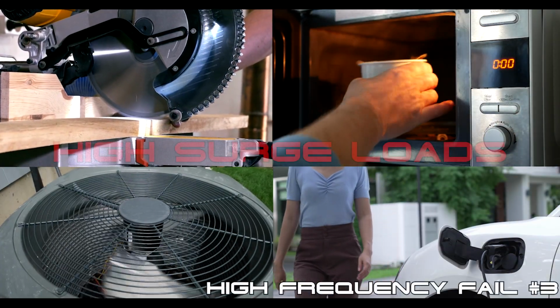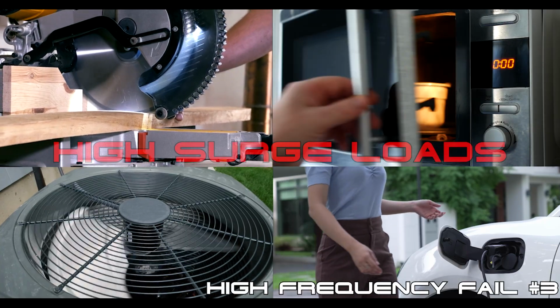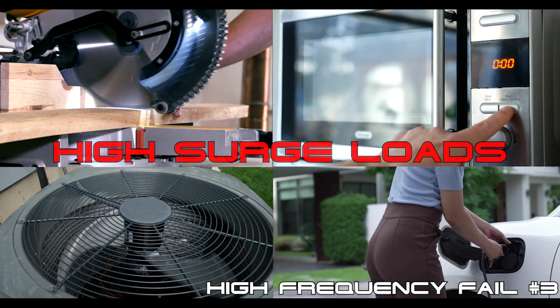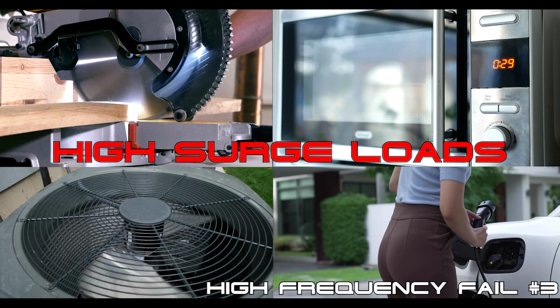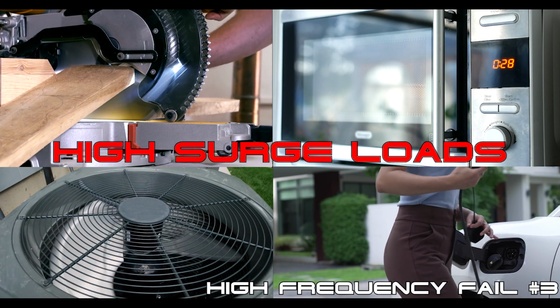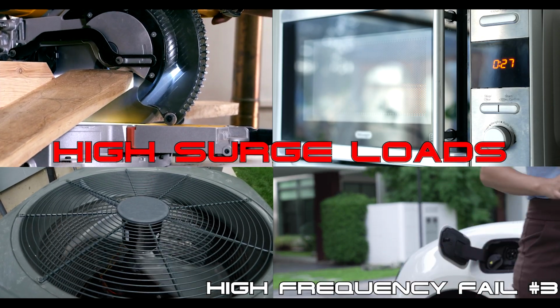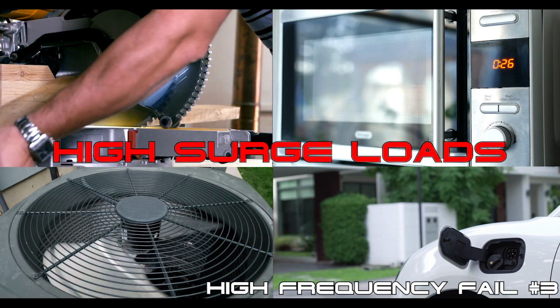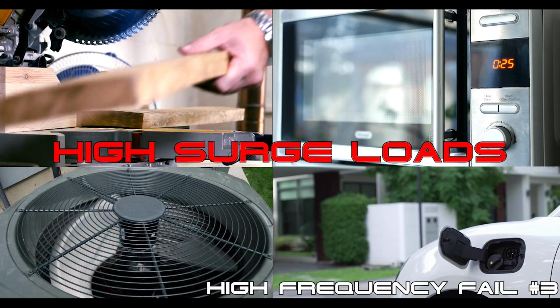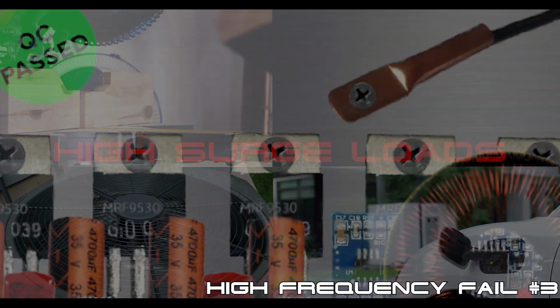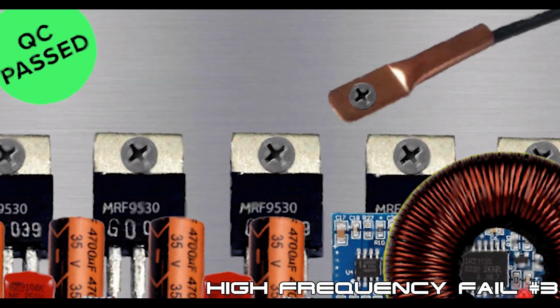High-frequency, transformerless inverters are not designed to repeatedly power high-surge loads such as refrigerators, microwaves, power tools, air conditioning, or EVs. You might be able to power some of these inductive loads when your high-frequency inverter is new, but every time you do, you're shortening the life of the already overheated MOSFETs and capacitors in your inverter.